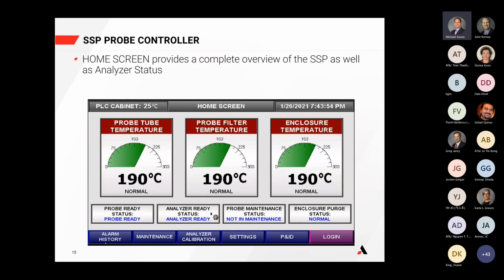Well, if that were the case, you'd have a message right here. But fortunately, everything in the system is working as it should. So the user is probably getting good results and valid results because the analyzer is not indicating any alarms. The probe, which is being monitored by this PLC controller or probe controller assembly, indicates that the probe is operating at proper temperatures and there's no alarms there. We're not in any kind of maintenance status, so nobody's gone in there and turned us off and put a hold current value situation on this assembly yet.